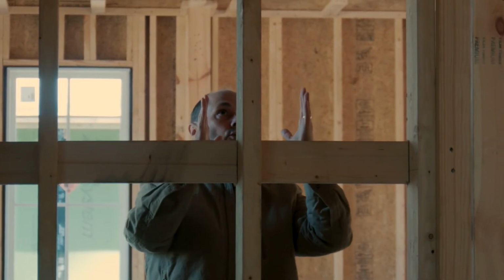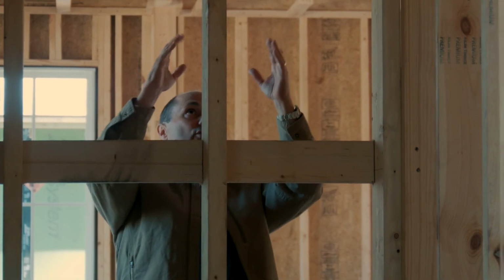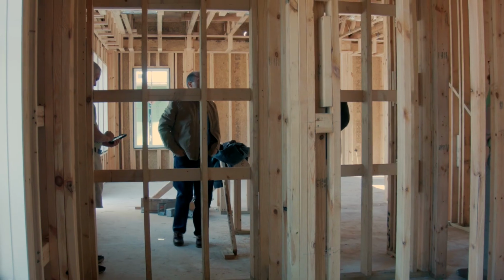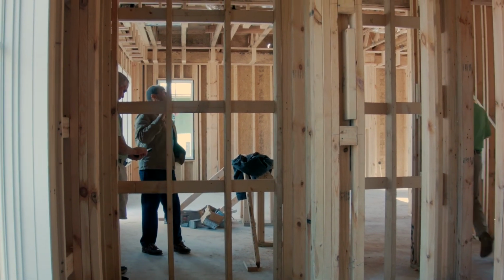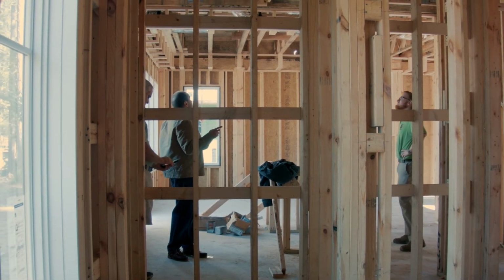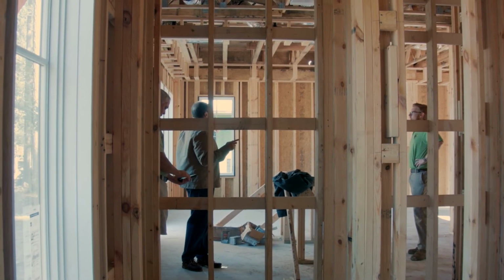If we did not have spray foam, if we had an air handler in a hot attic and ductwork in a hot attic, we would be at 2 tons easily, maybe even 2.5 on this job. But doing that ensures that the house leaks less air. It also ensures that if there are any losses from air handlers and ductwork, and there are, all air handlers leak a little bit, that those leaks are captured and contained in the home. We don't lose any of that air to the environment. We still keep it inside the home. So that brings the load down to 1.5 tons.